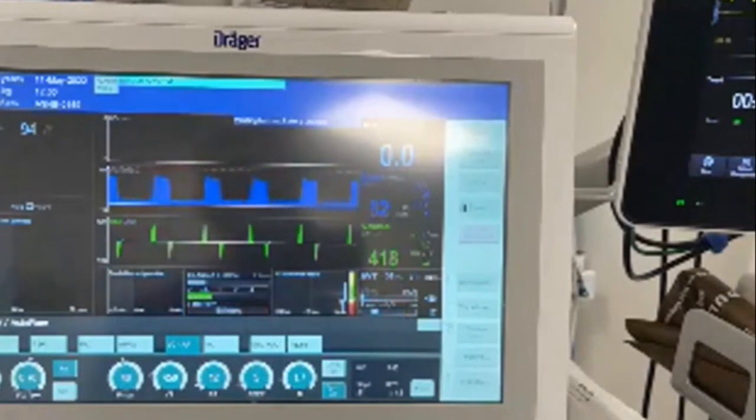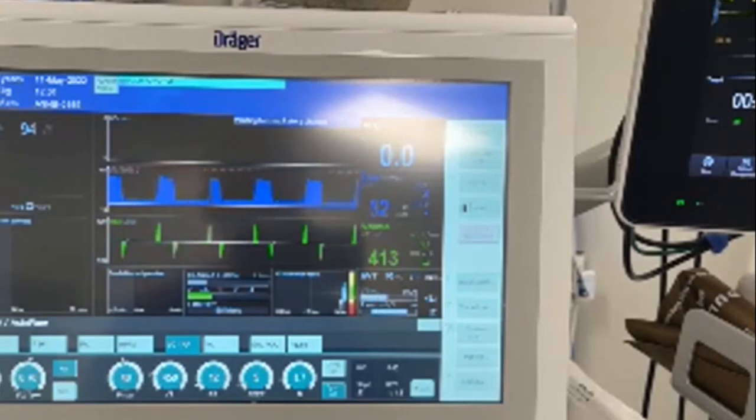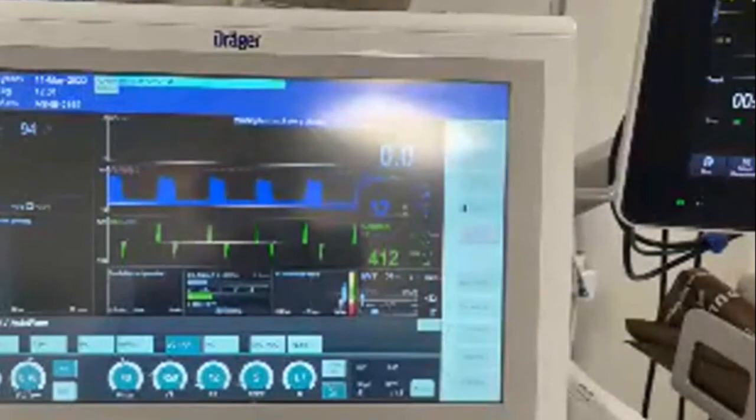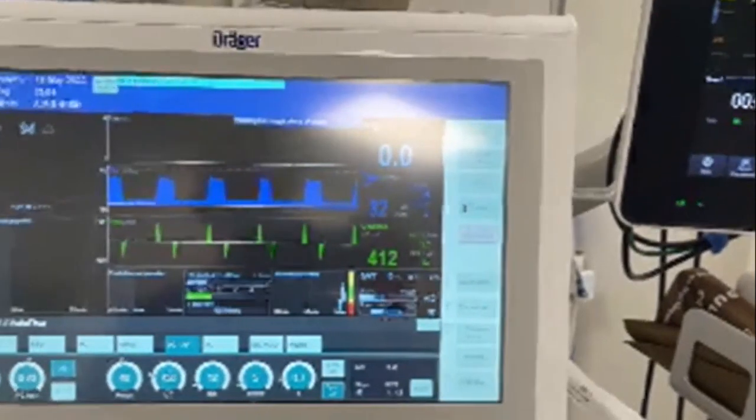There is evidence, Drager-sponsored evidence, that shows that the use of LowFlow Wizard is equivalent to end tidal control. And the Drager machines are more efficient than, say, for instance, GE machines at King's College Hospital that have end tidal control. So theoretically, we can even be more efficient than them because of the design of the actual ventilator, because of the turbine driven, and essentially it has a gas injector as opposed to a draw over vaporizer. That is everything that you need to be aware of.